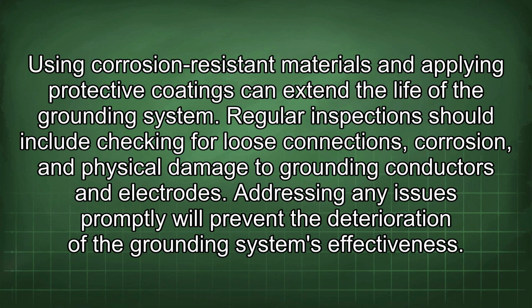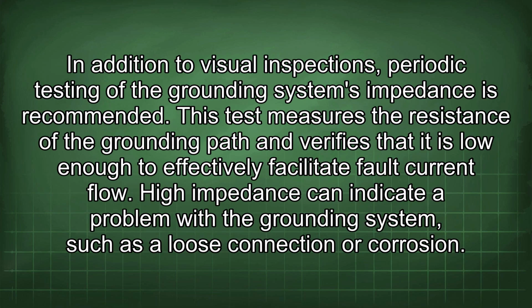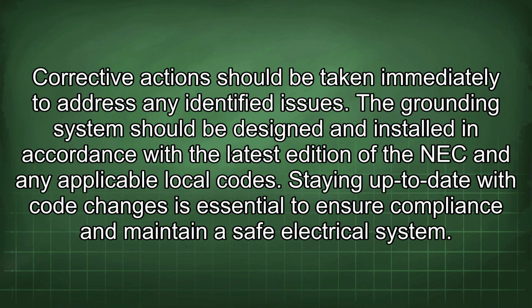Regular inspection should include checking for loose connections, corrosion, and physical damage to grounding conductors and electrodes. Addressing any issues promptly will prevent the deterioration of the grounding system's effectiveness. In addition to visual inspections, periodic testing of the grounding system's impedance is recommended. This test measures the resistance of the grounding path and verifies that it is low enough to effectively facilitate fault current flow. High impedance can indicate a problem with the grounding system, such as a loose connection or corrosion. Corrective action should be taken immediately to address any identified issues.